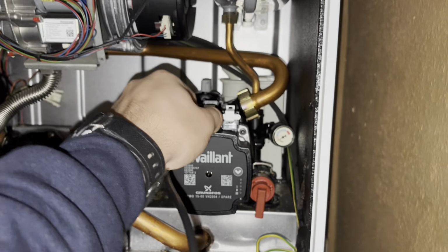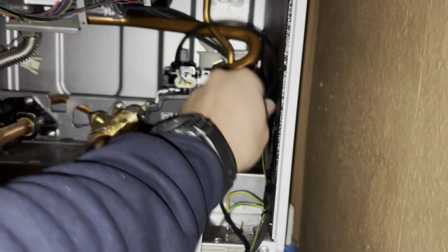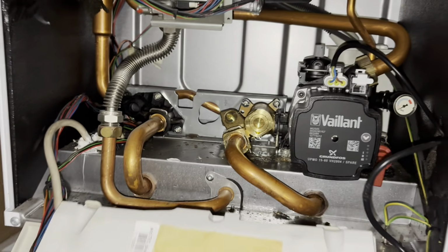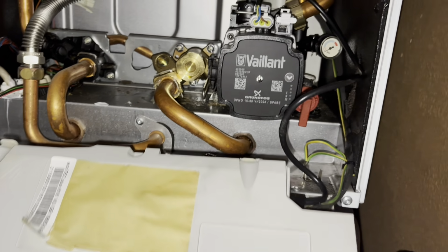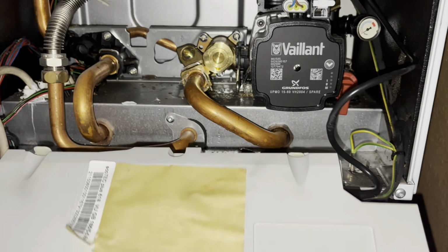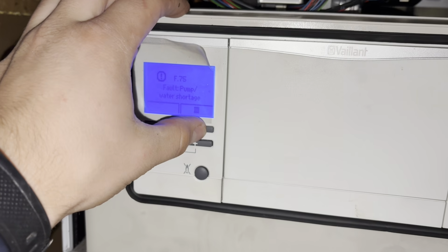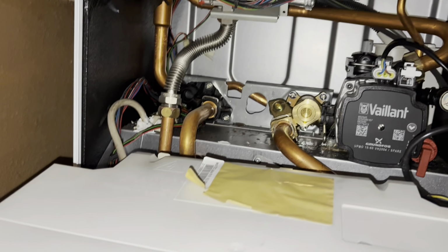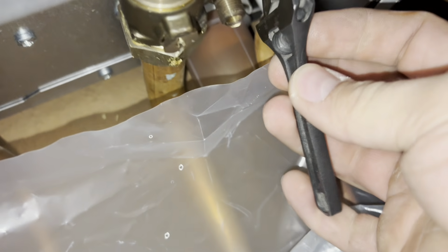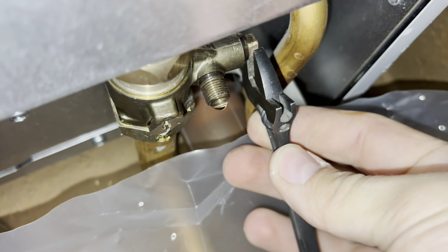Make sure that's dry. Cable, and then we will want to be, I'll give that a little wipe after I try to get that off. We want to be going to top up the boiler, make sure there's no leaks, and then test. So let me go find where the filling loop is. But yeah, before you top up, don't forget to close the drain off. So filling loop is right there.